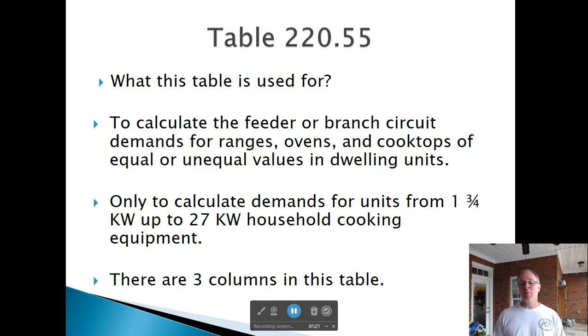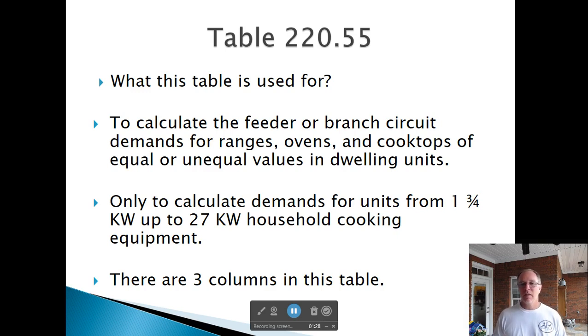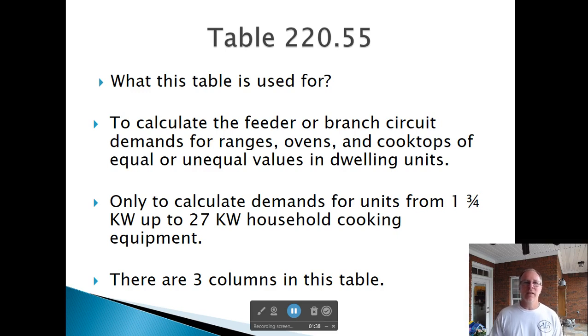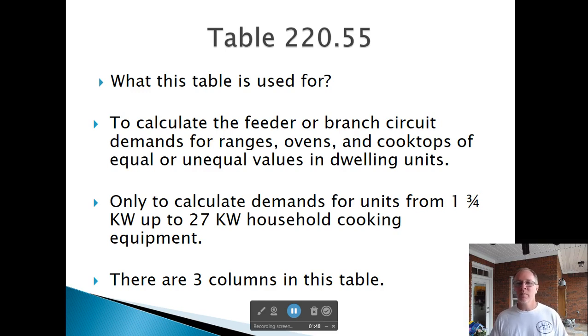If you've got 60 apartments and every one of them has a 12,000-watt range or oven, that's a lot of wire you don't need. Is everybody going to have their oven on at the same time? No. So we're trying to derate it and balance it out — kind of like how you don't turn all the lights on and the garage door and hot water heater and air conditioner on all at the same time.